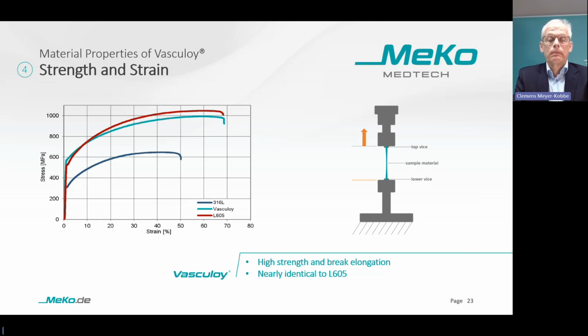You see three curves: stainless steel, so 316L, this is the blue one, L605 and Vasculoy. 316L has the lowest strength and is with only about 650 megapascal of strength without cracks. Also, the maximum strain is limited to about 50%. That means the tube can be elongated by 50% before it breaks. L605 and Vasculoy have much higher mechanical properties.